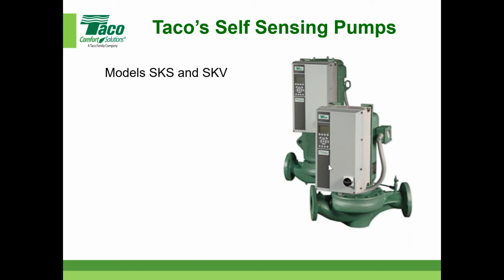Nonetheless, we put these pumps into our test stand and run them at different speeds, take all the data—flow, head, and whatnot—and put it into the lookup table that's embedded in the pump, so that pump stays on the curves. We have a whole hour presentation on demystifying these self-sensing pumps and getting into more detail on them.